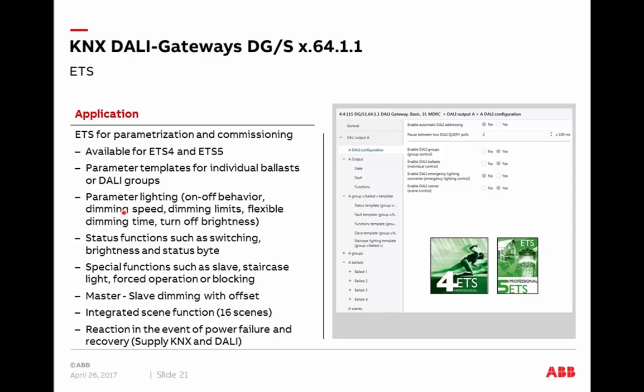Typical parameters include on-off behavior, switch-on and switch-off behavior, dimming speed, dimming limits, and turn-off brightness. A lot of status information can be enabled and sent on the bus as telegrams. Further functions include slave function, staircase function, forced operation — such as setting a lamp to a fixed level like 70% — and blocking channels or ballasts. Master-slave dimming allows one master to also control a slave circuit in parallel, potentially with an offset so the slave channel dims to a lower level.